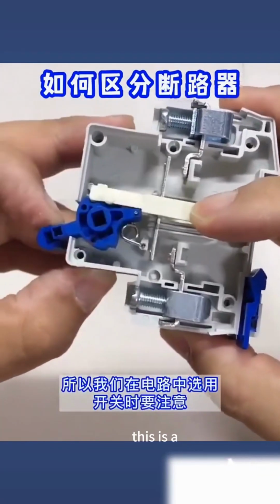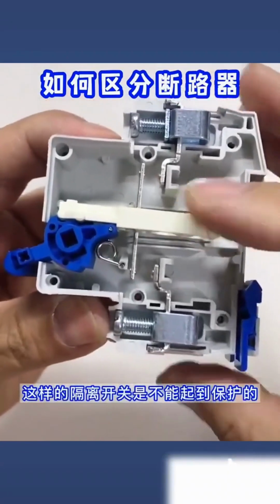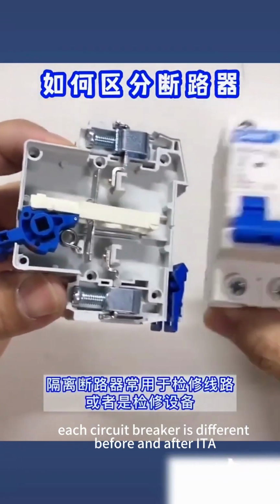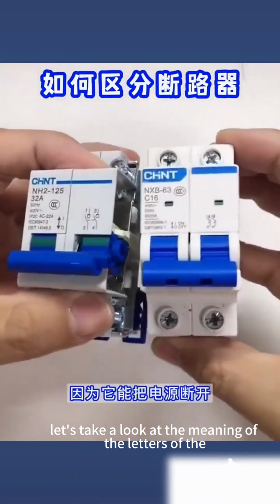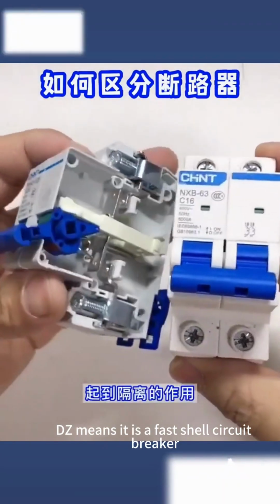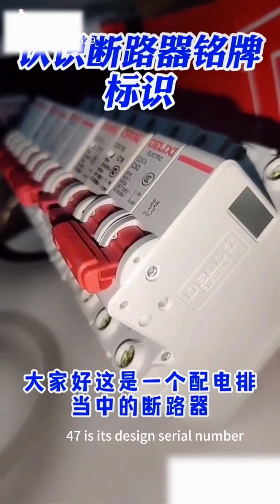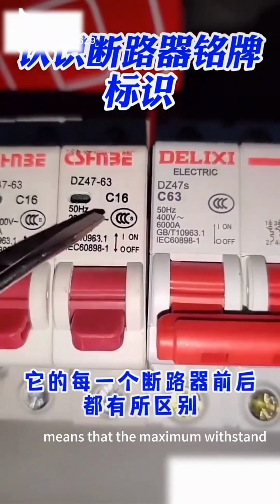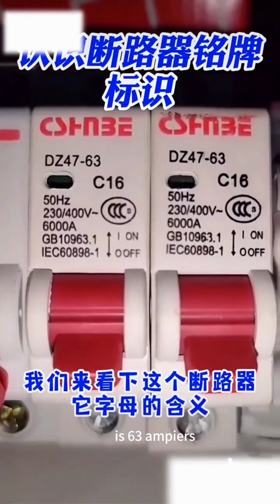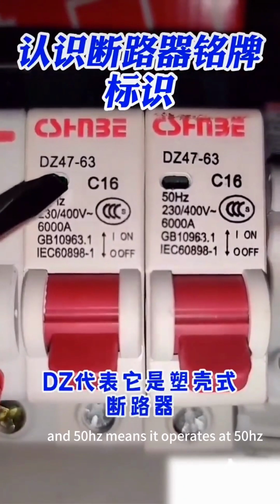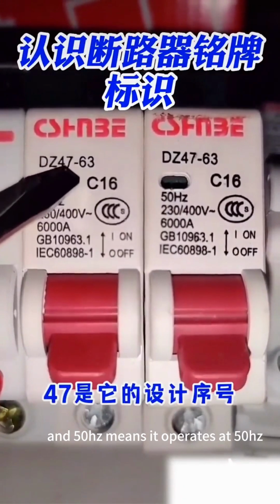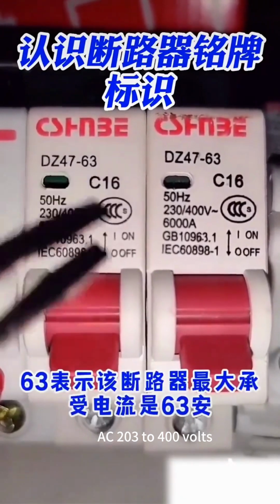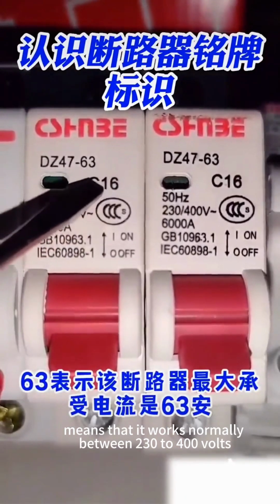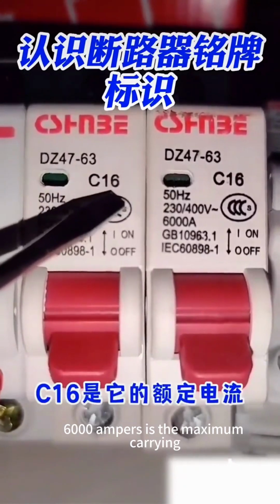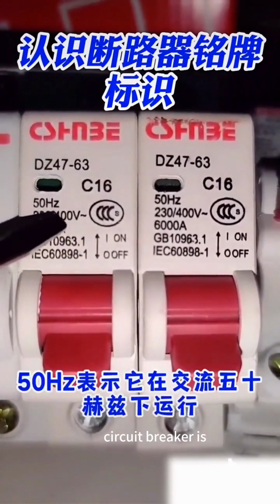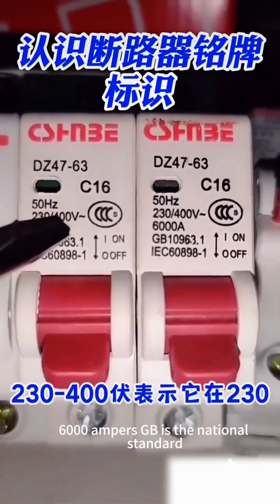Hello everyone, this is a circuit breaker in the middle of a distribution row. Each circuit breaker is different. Let's take a look at the meaning of the letters on this circuit breaker. DZ means it is a molded case circuit breaker, 47 is its design serial number, and 63 means that the maximum rated current of the circuit breaker is 63 amperes. C16 is its rated current, and 50 Hz means it operates at 50 Hz AC. 230 to 400 volts means that it works normally between 230 and 400 volts. 6000 amperes is the breaking capacity of this molded case circuit breaker. GB is the national standard.